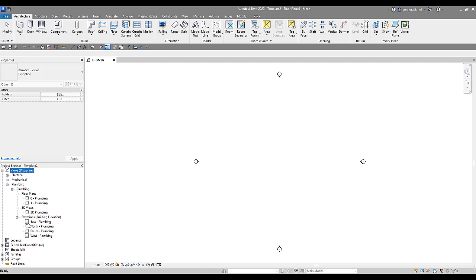The sheet-ready classification are all of the views that are ready to go and be placed onto a sheet. Those views, for the most part, are going to have your view templates set up for you. Everything is going to be essentially ready to go, as close as you can get to being ready to go to be placed onto a sheet. The working classification, if a view is placed under the working classification, those are views that you're going to be doing your modeling in. You're going to be doing all of your modeling, modeling duct piping, placing elements, placing mechanical equipment. All that kind of stuff is going to be done in your working views. Your sheet-ready views, they're going to be pretty much all done for you, except that's where you're going to go through and add notes. You're going to add your annotations in your sheet-ready views. No modeling will be done in your sheet-ready views.